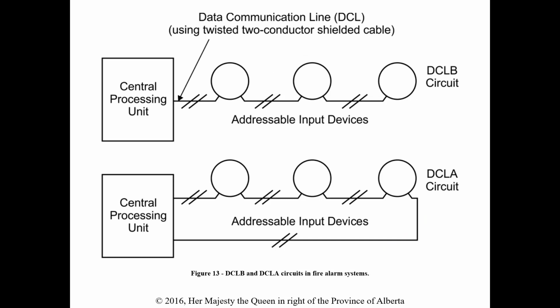Addressable devices. The big thing with addressable devices is the benefit of knowing where the issue potentially is. We can still have an A or B, they call them DCL or data communication line. There's basically a wire going to each device, and each one of them is talking back to the CPU constantly. It's constantly saying, I'm here, I'm good, I'm ready to go, and it's sending that signal back all the time. If for some reason it's not ready to go, then we're going to get a trouble signal.